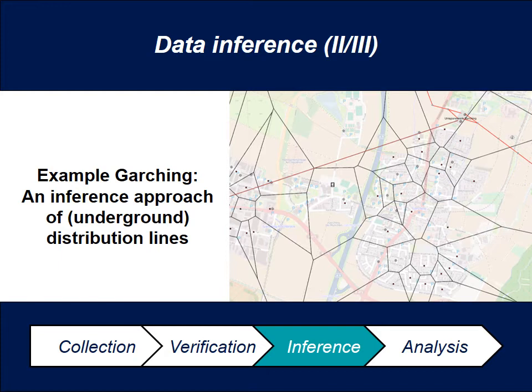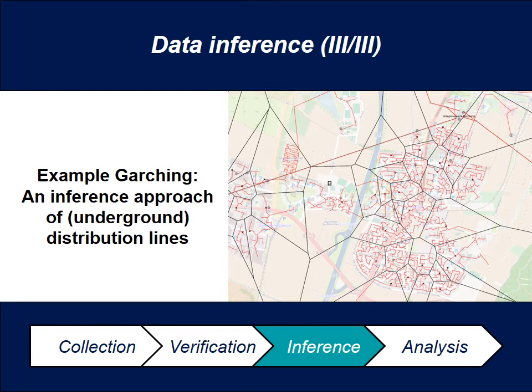This is an example for the city of Garching to do an inference on how the power lines could look. We have the transformers, and the first thing we do is a Voronoi partition in order to segment the area and assign transformers that are supposed to supply a certain amount of houses. Once you have the segmented area, you connect the transformer to all the houses in each section.